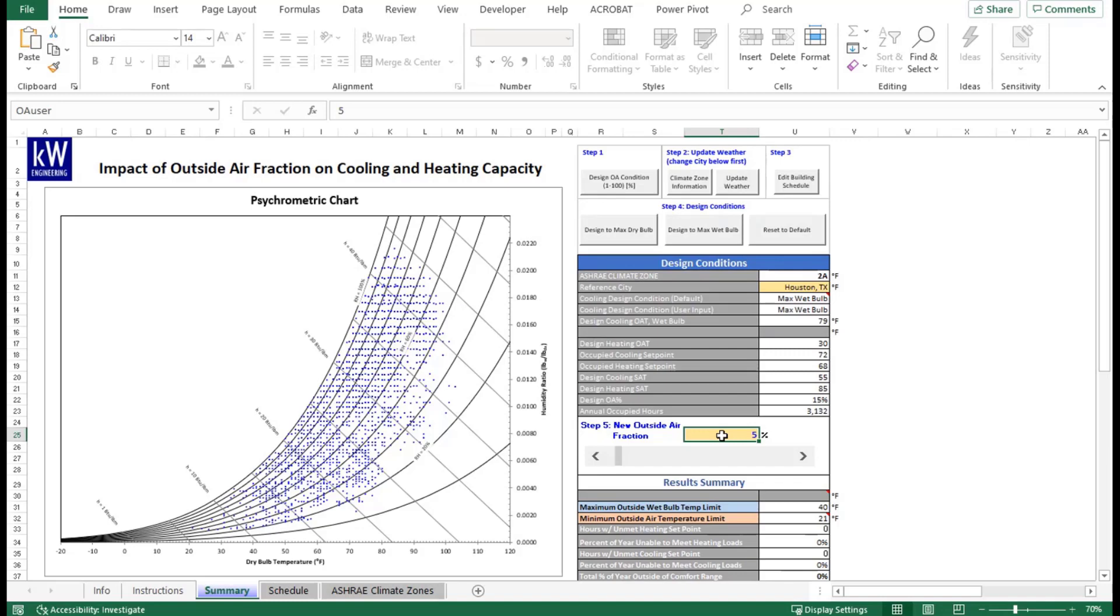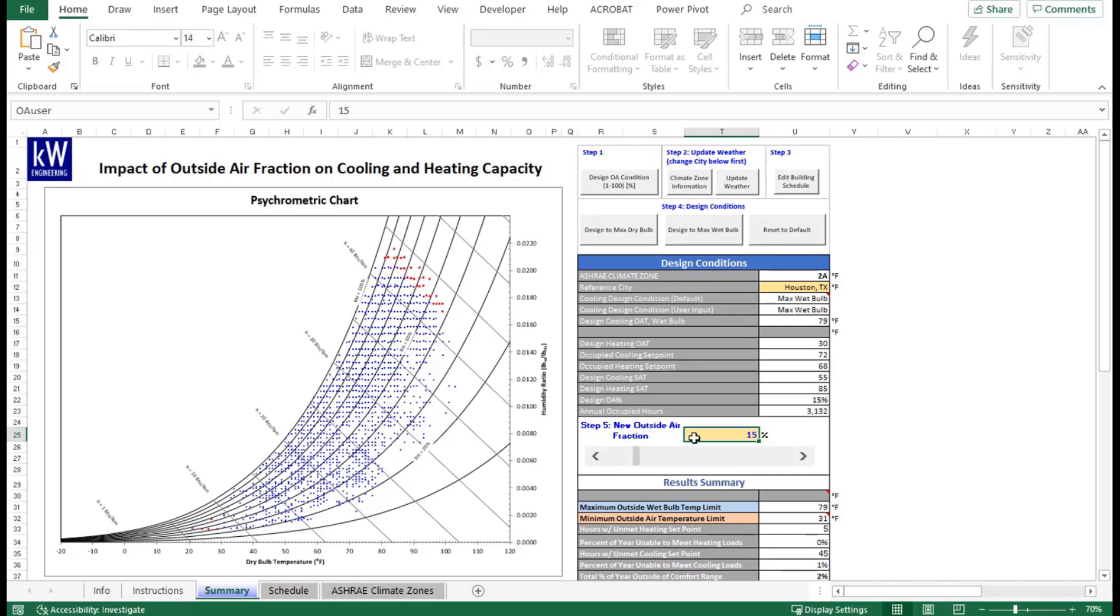But now, what happens if we increase it above that threshold? That's when you start running into issues. You can either update it through using cell T25 or using the slider tool here. I like to use that one preferably. It does increase in 10% intervals. The first increase shows that it's now at the design condition. The design does account for meeting 99% of the loads throughout the year. That's why you see a little bit of the red dots here. But the majority of the year, it is capturing everything.